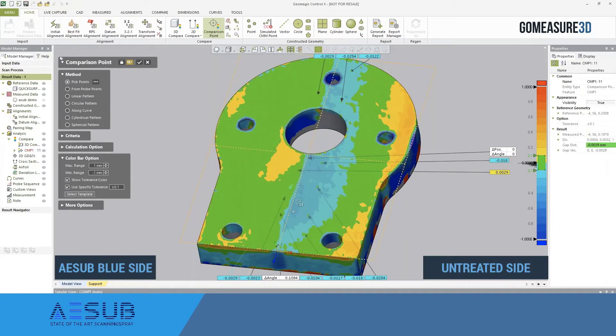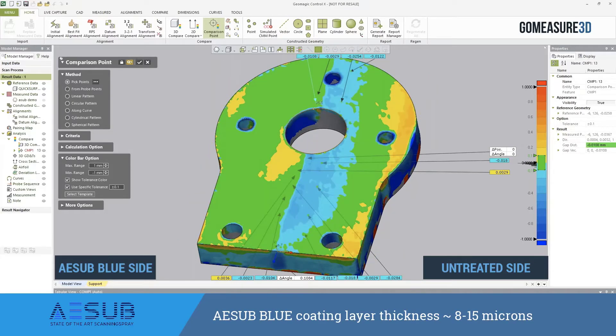The deviation number we come up with is about 18 microns of variation from the AESUB side to the aluminum side, which when we look at the specs of AESUB actually falls outside of what the specified thickness of the spray is — which is 8 to 15 microns.